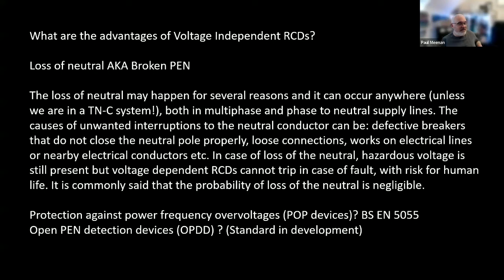What are the advantages of voltage independent? Well, loss of neutral. This is directly from a white paper. The loss of neutral may happen for several reasons, anywhere unless we're in a TNC, which we don't recommend. Both in multi-phase and phase to neutral supply lines, unwanted interruptions to the neutral conductor can be caused by defective breakers that do not close a neutral, loose connections, or works on electrical lines or nearby electrical conductors. In the case of a loss of neutral, hazardous voltage is still present, but voltage-dependent RCDs cannot trip in case of this fault. There is a risk for human life. It is commonly said that the probability of loss of the neutral is negligible, but as you can see, it is growing. So we need to be mindful of it.